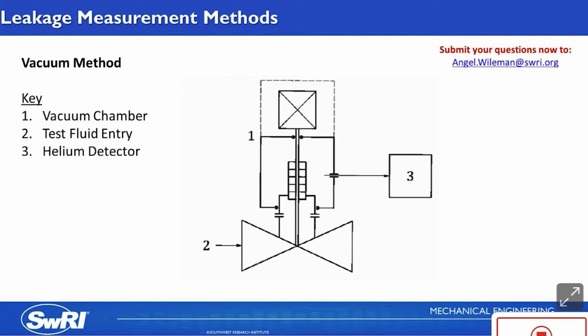The chamber can't interfere with valve actuation, or else you're going to have problems doing your mechanical cycles, and it can be removed during thermal cycling if needed to avoid overheating. The operator must check the vacuum tap running to the mass spec is positioned correctly, and they also must make sure that nothing's clogging the line that runs to the mass spec.